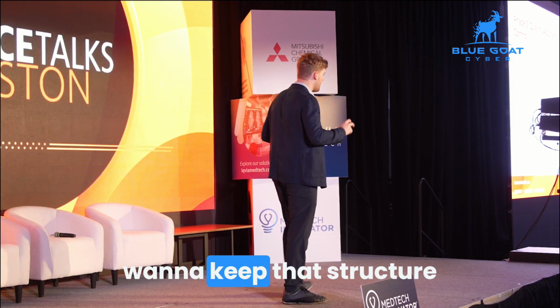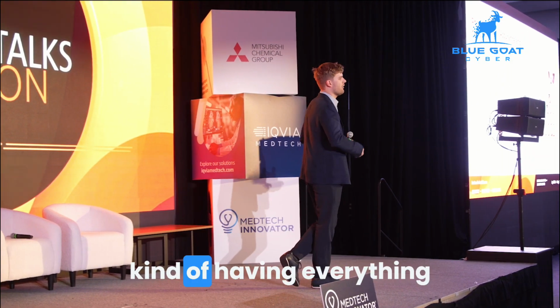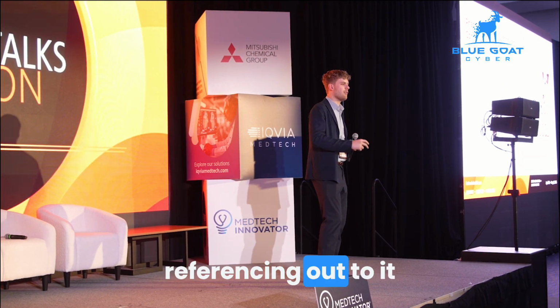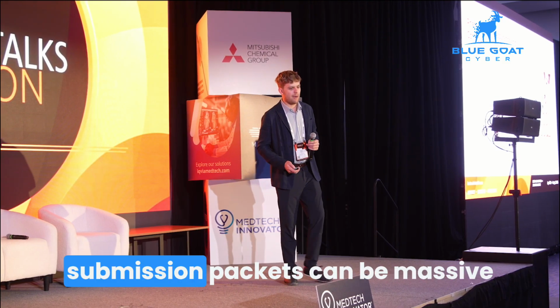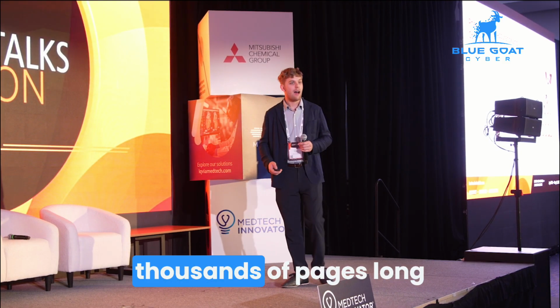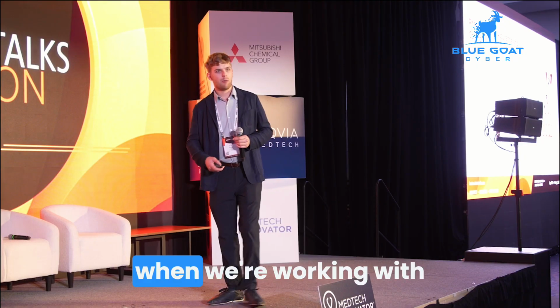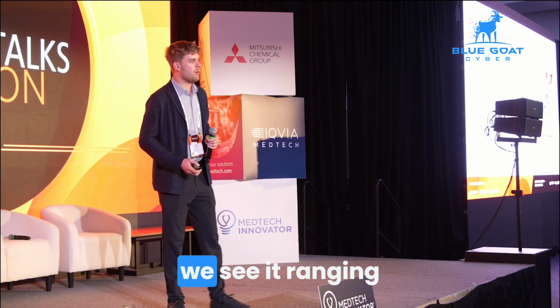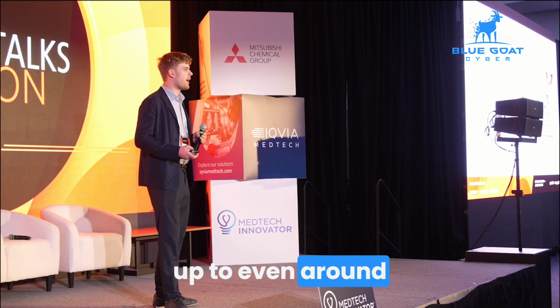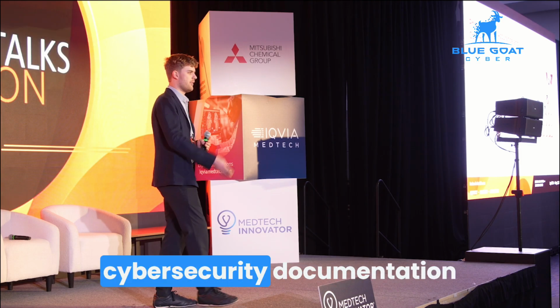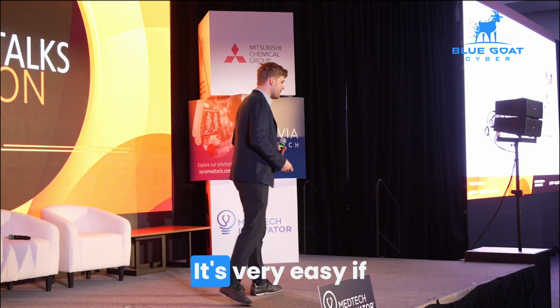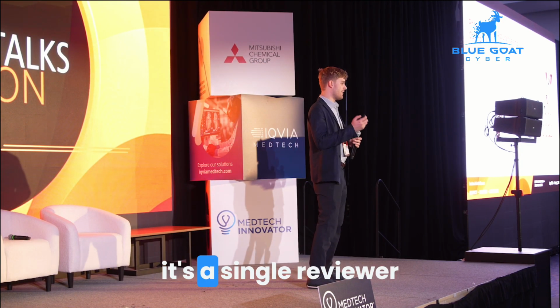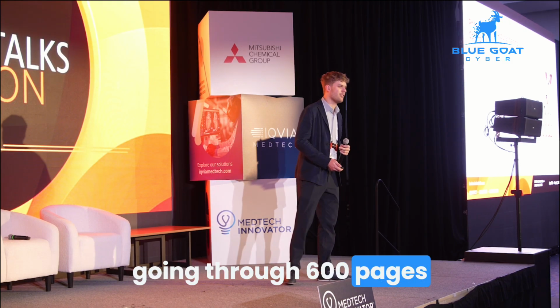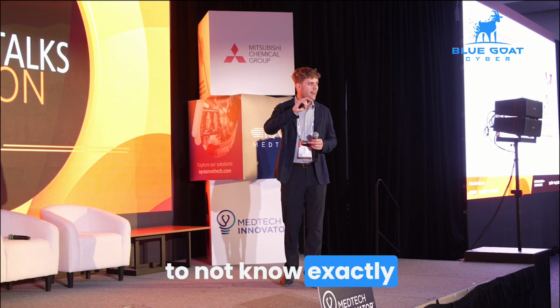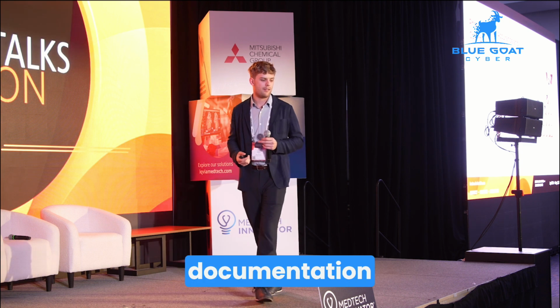We need to make sure that everything is structured in that fashion. And the reason we want to keep that structure precise, instead of just having everything in one place and referencing out to it, is that some of these submission packets can be massive, thousands of pages long. Typically, when we're working with a cybersecurity packet, we see it ranging up to even around 600 pages purely of cybersecurity documentation. It's very easy, if it's a single reviewer going through 600 pages, to miss something or to not know exactly the structure of how you're handling your documentation. That's why we want this to line up with eSTAR.